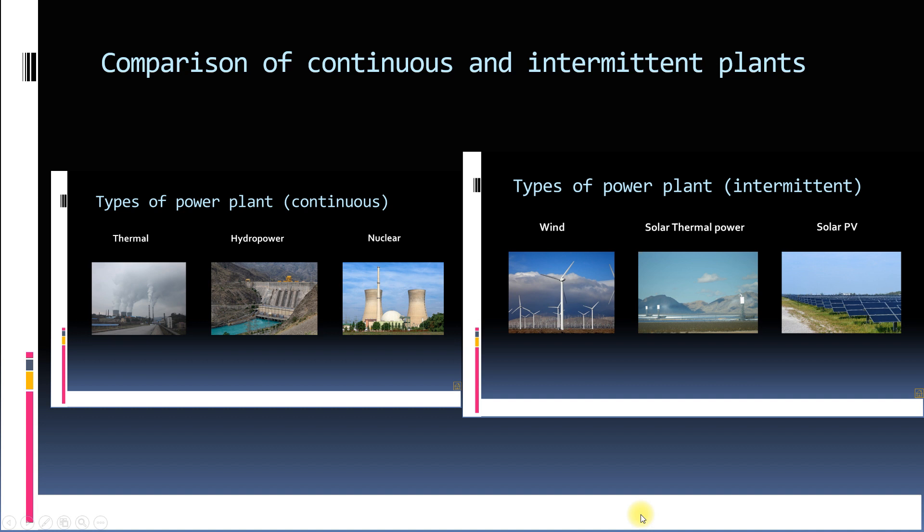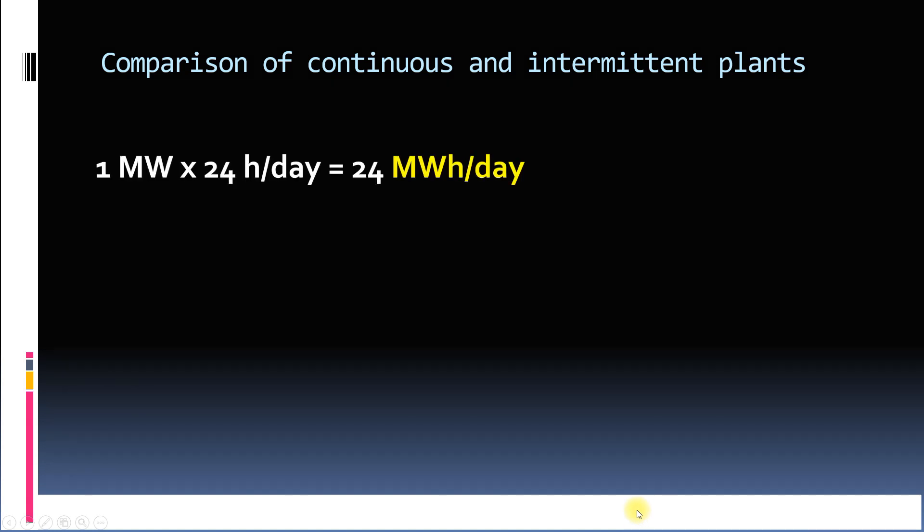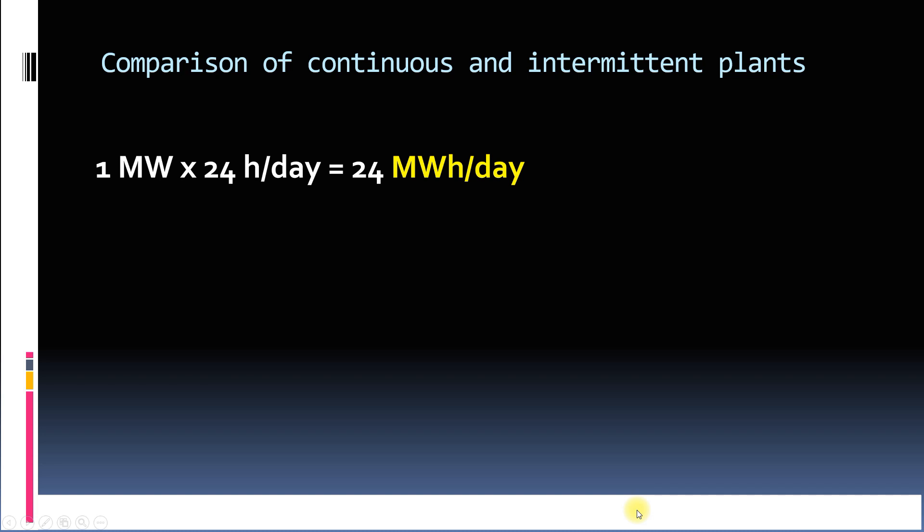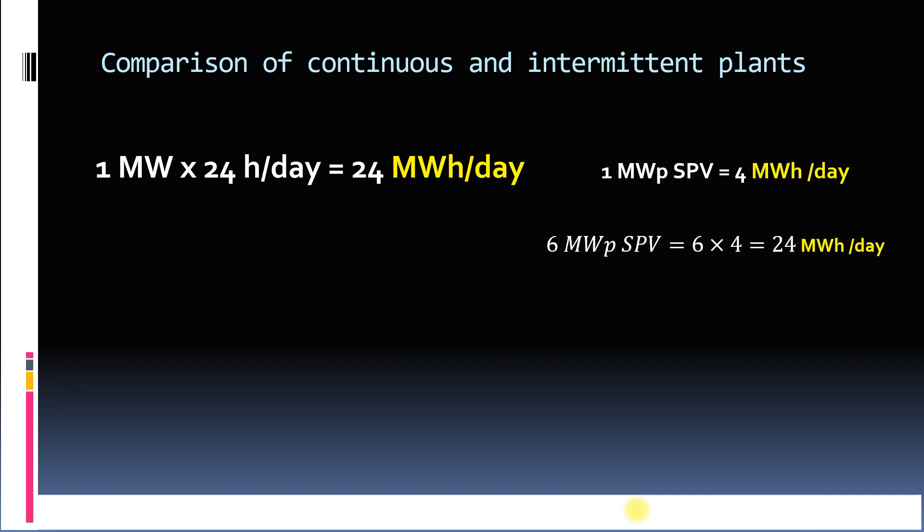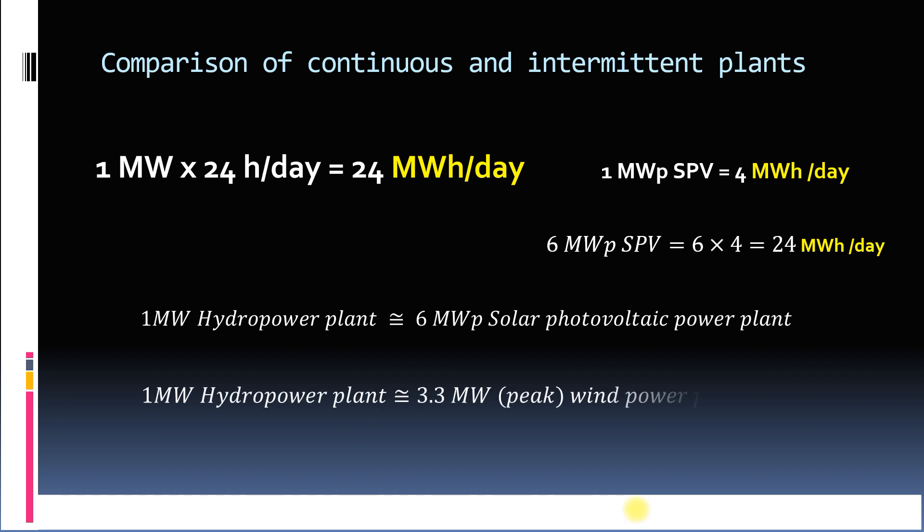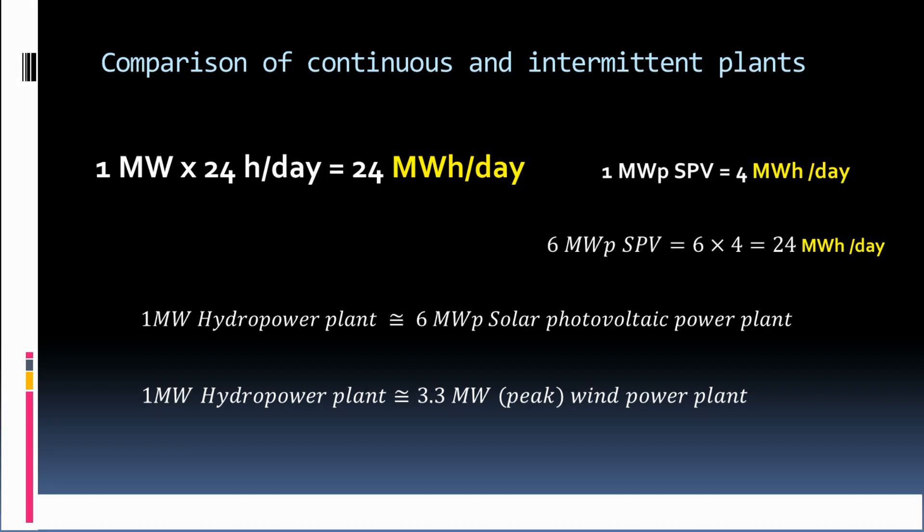Let's compare now continuous and intermittent power plants. We know that 1 megawatt continuous power plant will supply 24 megawatt hours of electricity in a day if it runs for 24 hours. Whereas, a 1 megawatt peak solar power plant in India will give around 4 megawatt hours per day. So, a 6 megawatt peak solar power plant will give around 24 megawatt hours of electricity per day. So, we can say on the basis of energy that 1 megawatt hydropower plant is equivalent to 6 megawatt peak solar photovoltaic power plant. A similar argument can be given that 1 megawatt hydropower plant is equivalent to 3.3 megawatt peak wind power plant on the yearly basis as it supplies energy only 30% of the time.